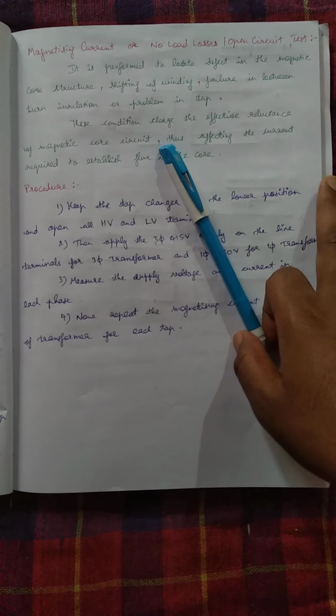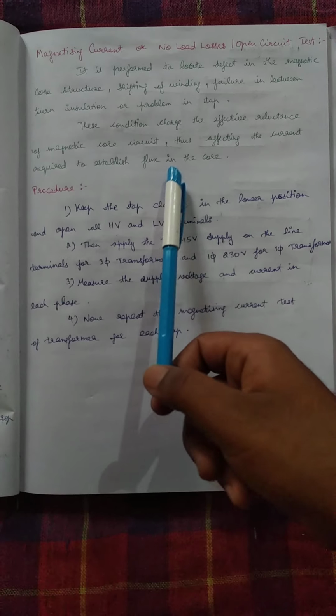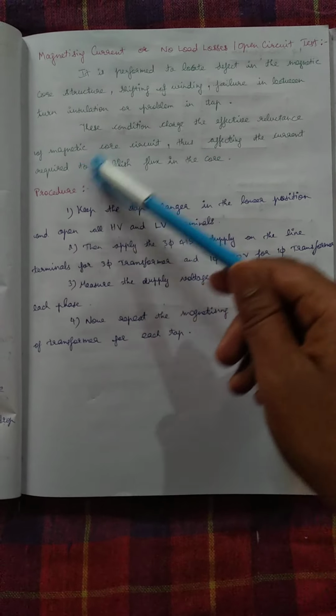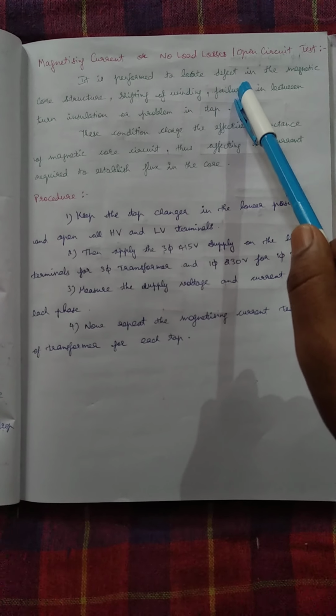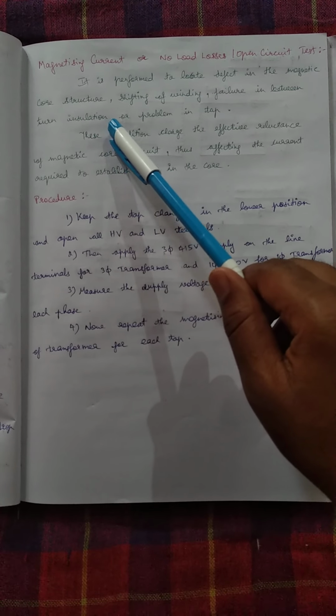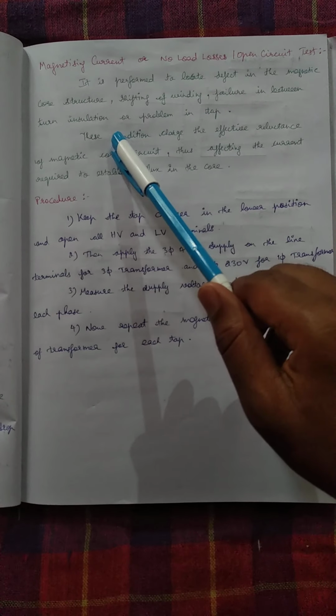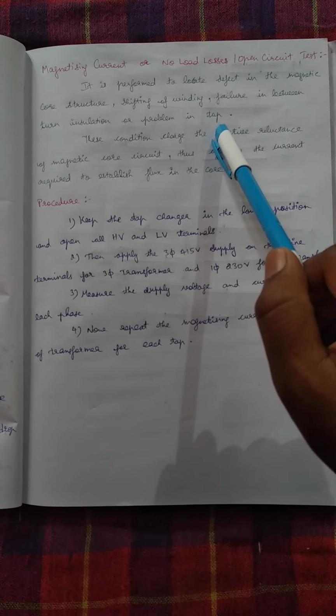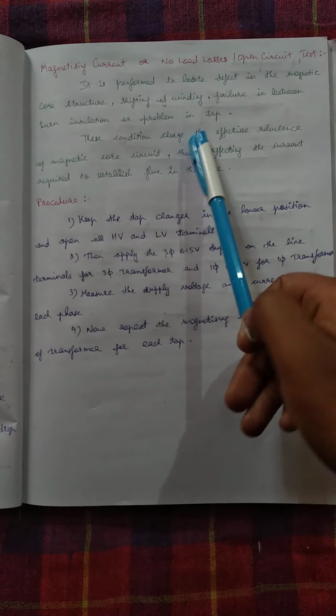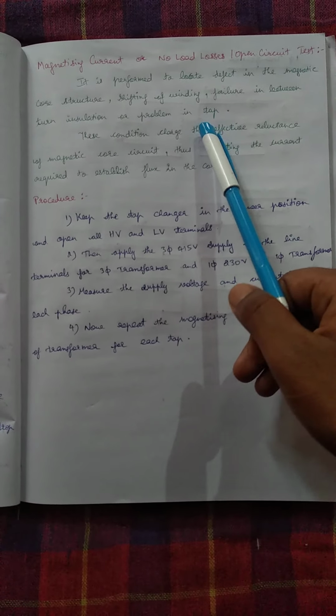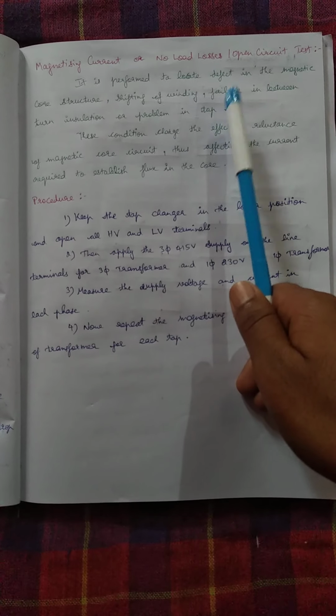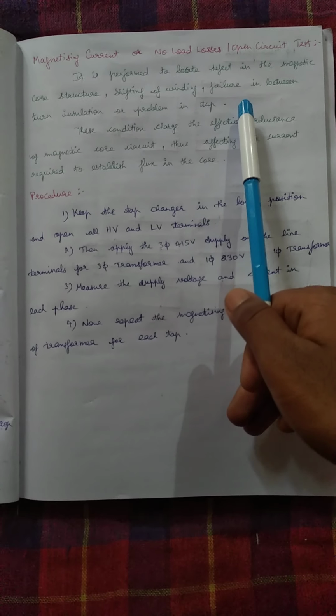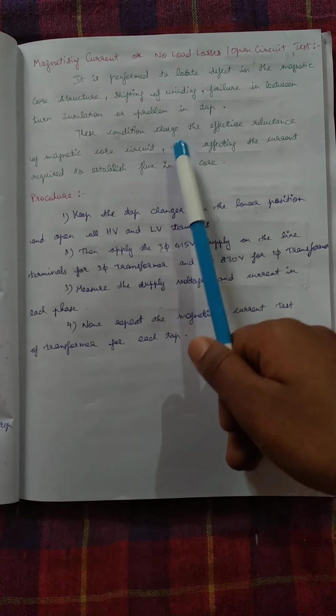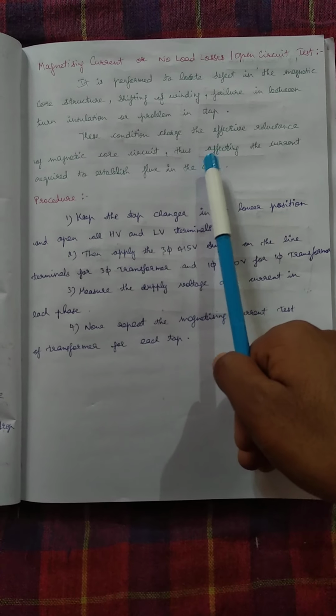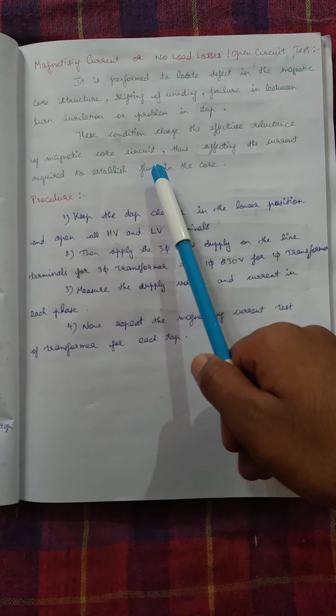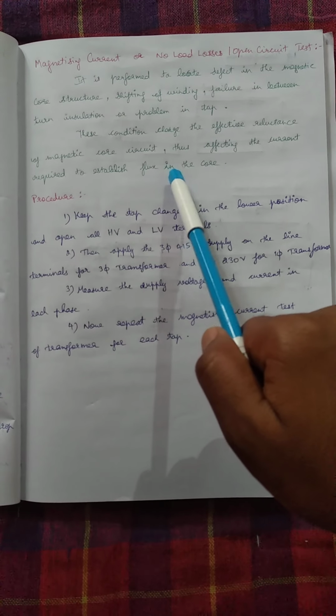Mostly the current will be measured at the milliamp level only. It is preferred to locate a defect in the magnetizing core structure, shifting of winding, failure between the turns, insulation, or a problem in the taps. If there is any problem inside the transformer or the winding, or even if we have missed any connections between the taps, this no load loss will be higher, and then we can easily understand that there is a problem in the magnetizing current. This condition changes the effective reluctance of the magnetizing core circuit, thus affecting the current required to establish a flux in the core.